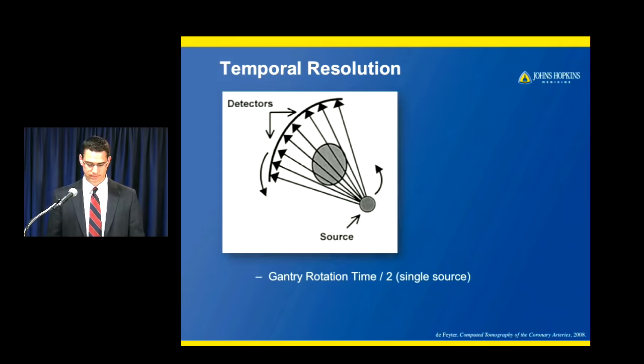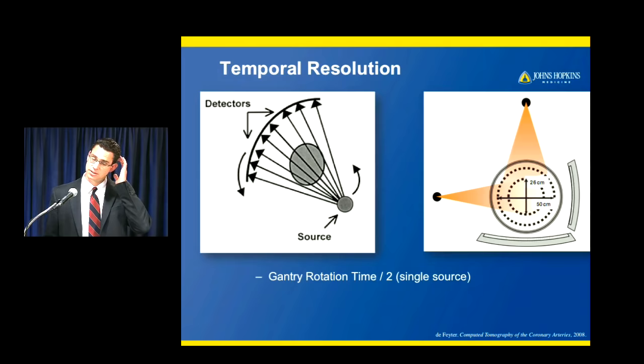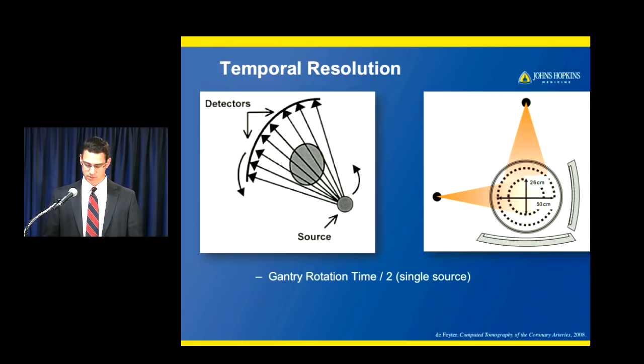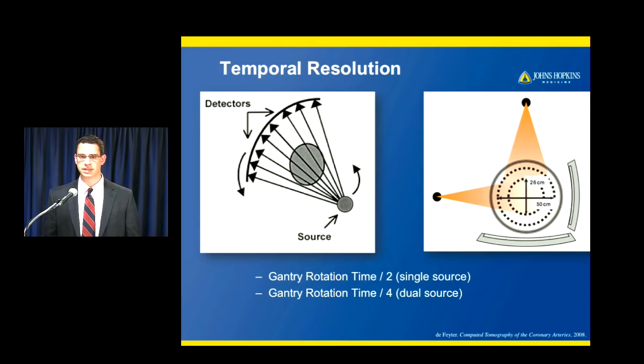There's an exception becoming more common: dual source scanning. With two x-ray tubes, each can independently contribute 90 degrees of data, so we only need to go one quarter of a revolution to get 180 degrees of projection data. For dual source imaging, temporal resolution is approximately the gantry rotation time divided by four. With typical gantry rotation times of 250 to 330 milliseconds, that gives a range of roughly 63 to 135 milliseconds for currently available CT scanners.